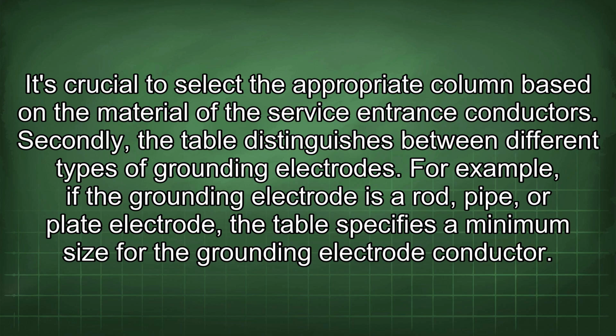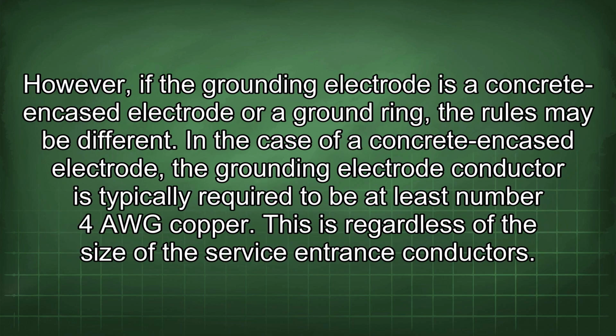Secondly, the table distinguishes between different types of grounding electrodes. For example, if the grounding electrode is a rod, pipe, or plate electrode, the table specifies a minimum size for the grounding electrode conductor. However, if the grounding electrode is a concrete encased electrode or ground ring, the rules may be different. In the case of a concrete encased electrode, the grounding electrode conductor is typically required to be at least number 4 AWG copper. This is regardless of the size of the service entrance conductors.